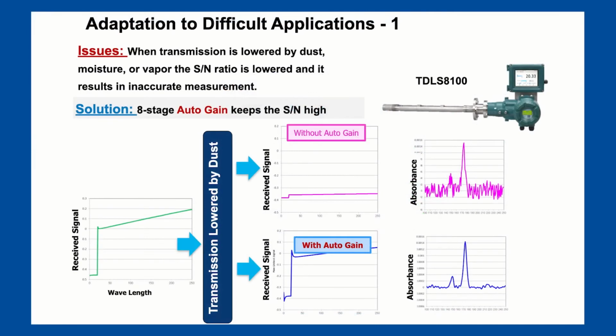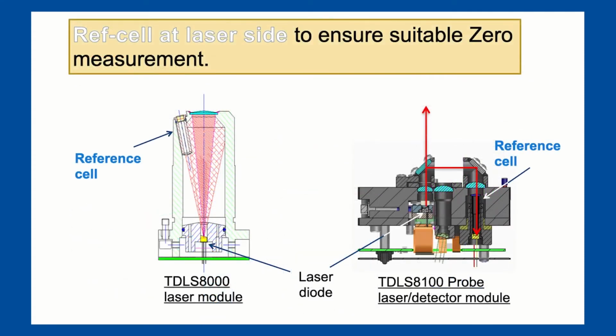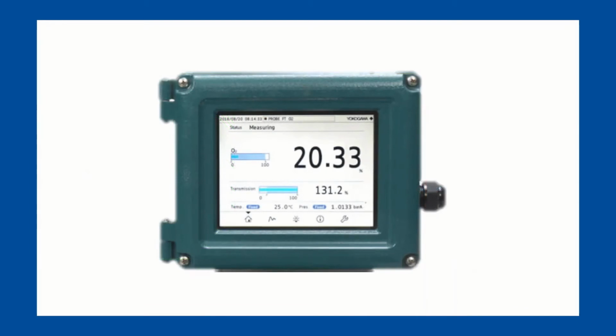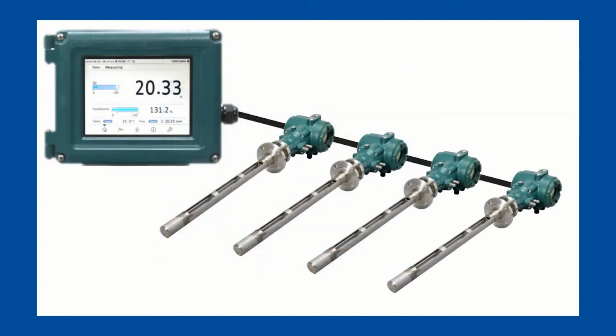Eight stages of auto gain keep the signal optimized in case windows become contaminated from inadequate window purge. Our integral reference cell also maintains the measurement wavelength so that validations or specialty line locking gases are not required when your target gas isn't present in process. The platform shares the HMI from the TDLS8000 series for a user-friendly interface, which is also available via free software for remote maintenance terminals. The HMI can communicate with up to 4 analyzers simultaneously.